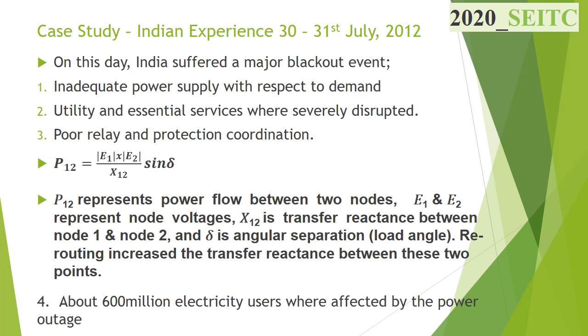There was appreciable current flow through the line, and inadequate reactive power compensation gave rise to a reduced voltage profile. This condition was sensed as a fault by the distance relay and therefore actuated trip action on the transmission line. Following the tripping of the 400 kV line, power to the northern region was routed through the eastern region. The new path, western region to eastern region to northern region, is much longer than the previous one. This gave rise to larger angular separation between the group of machines in the western region and the northern region.